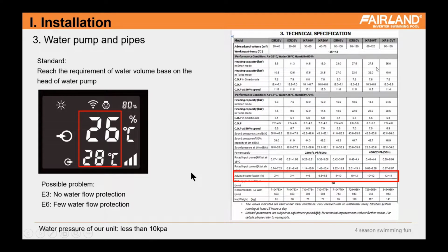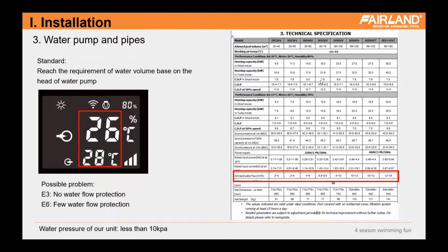And sometimes the customer will ask, they don't know if the water pump already provides a proper water volume, and we will let them check the inlet water and outlet water temperature. Normally, after 10 minutes of stable running, if the difference is 2 or 3 degrees, then it is fine. The water flow volume is fine. And if there is no water, sometimes the customer will suffer a problem when installing the units with the water system, the water pipe. It's E3.